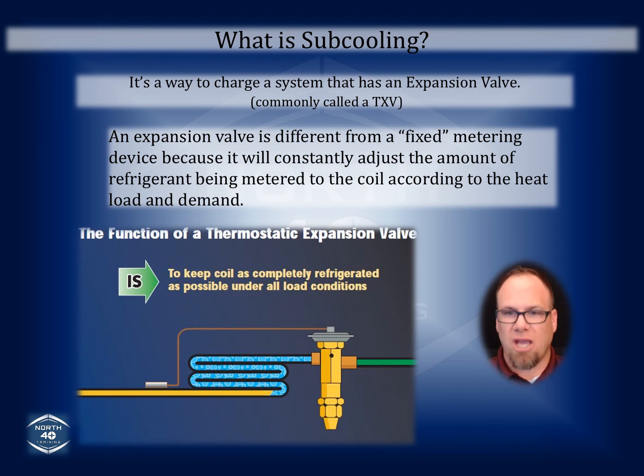Okay, once you check those things, I don't need a card or any of those things to check that. I don't need to have backup notes. I can subtract the temperature on the gauge, the temperature on the line set. Right? What are we talking here? Somewhere between 6 and 20. I can subtract that much. You can subtract that much. So don't be tied to some kind of card or chart on that.